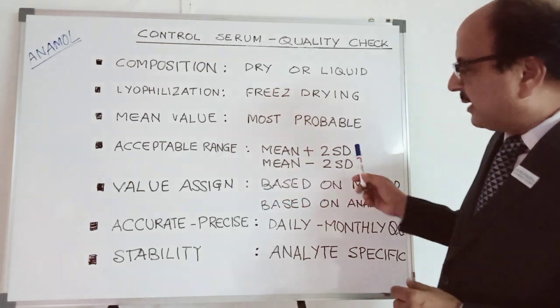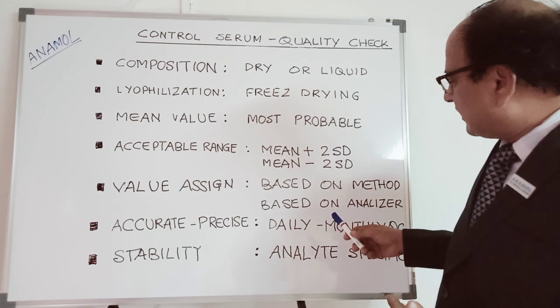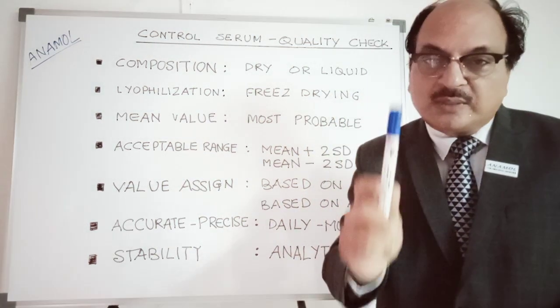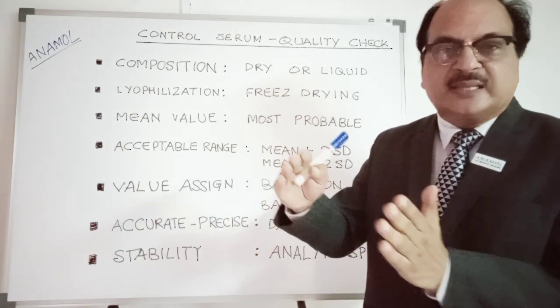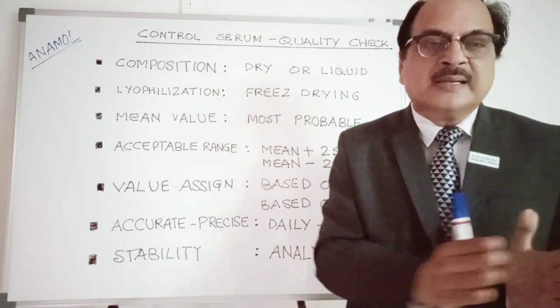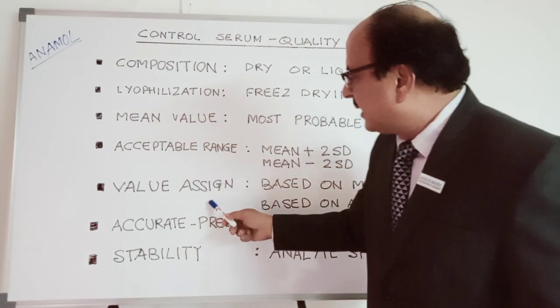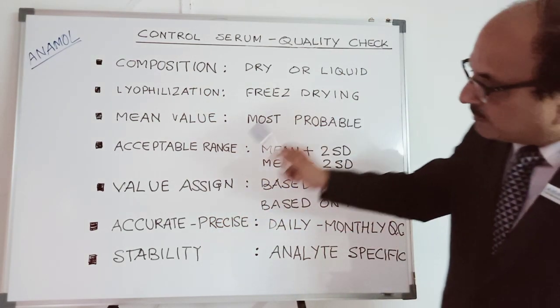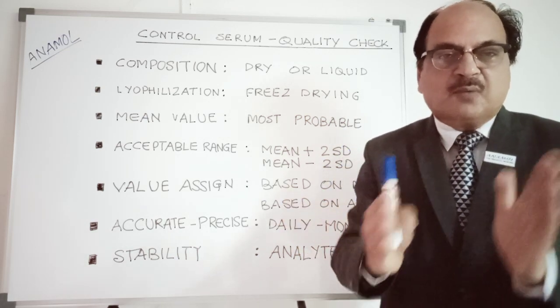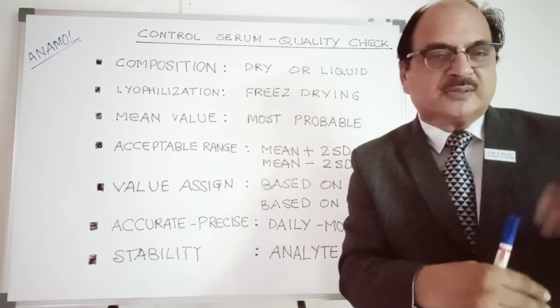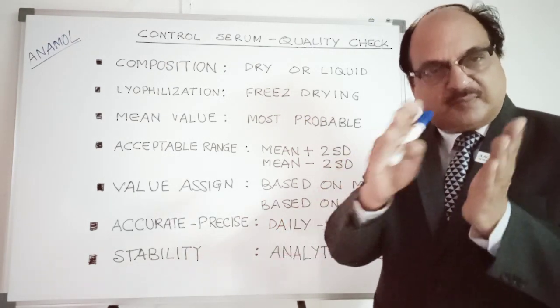Once you understand mean and acceptable range, it's important to know how values are assigned. Values are assigned based on methodology — for HDL analysis, you can use the precipitating method or the direct homogeneous method. Control serum manufacturers specify the value based on method, so for one analyte you get values for multiple methods, each with a mean value and acceptable range.